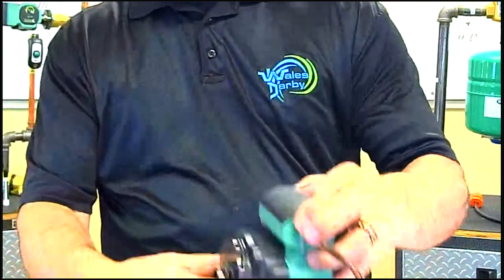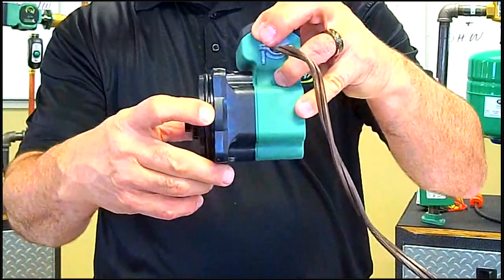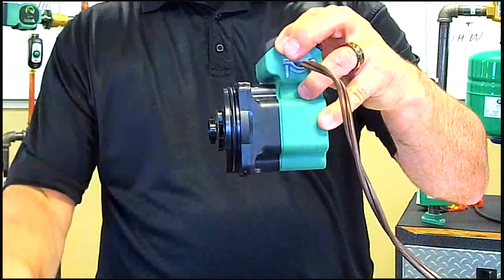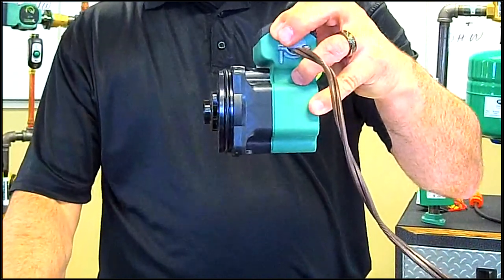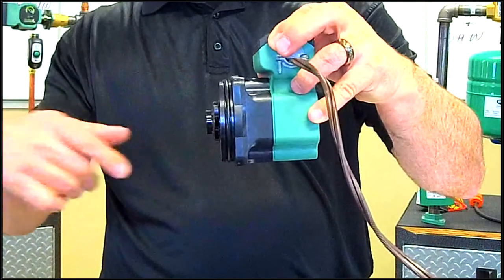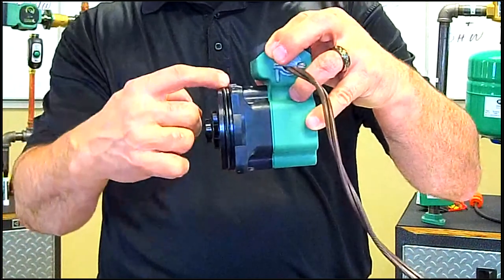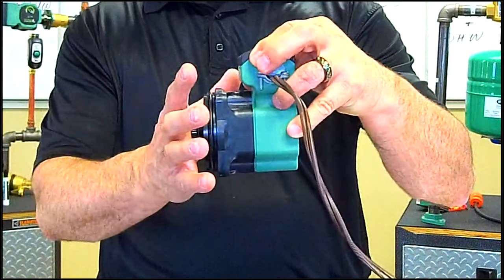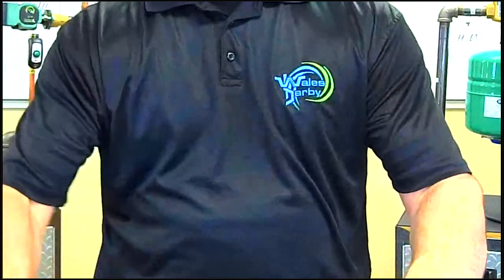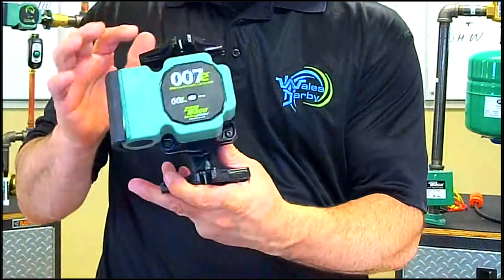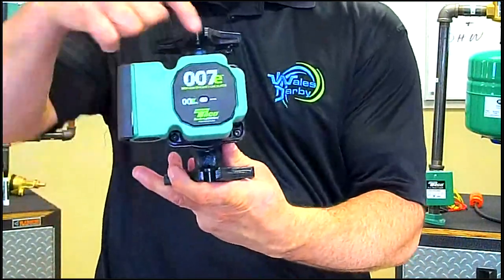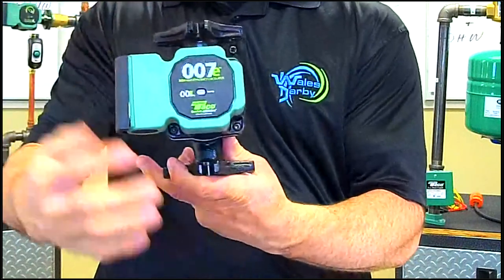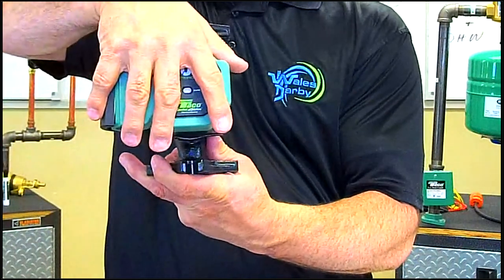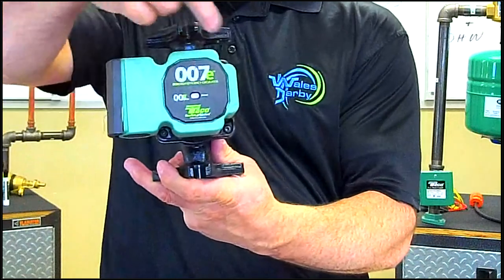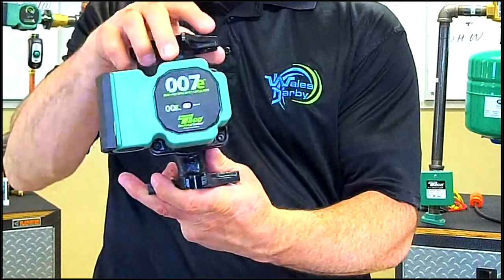The reason we say that is there's a rubber O-ring right here, and that rubber O-ring is captured inside of the body. If you pull that motor out, you may have a difficult time getting that rubber O-ring back into the housing. So if you need to rotate it, I don't want to kill this, but I want to make sure nobody has a problem at 6 o'clock at night. Pull the four Allen keys out, just rotate your motor while the O-ring is still in the housing, and then put your Allen keys back in and you're ready to go.